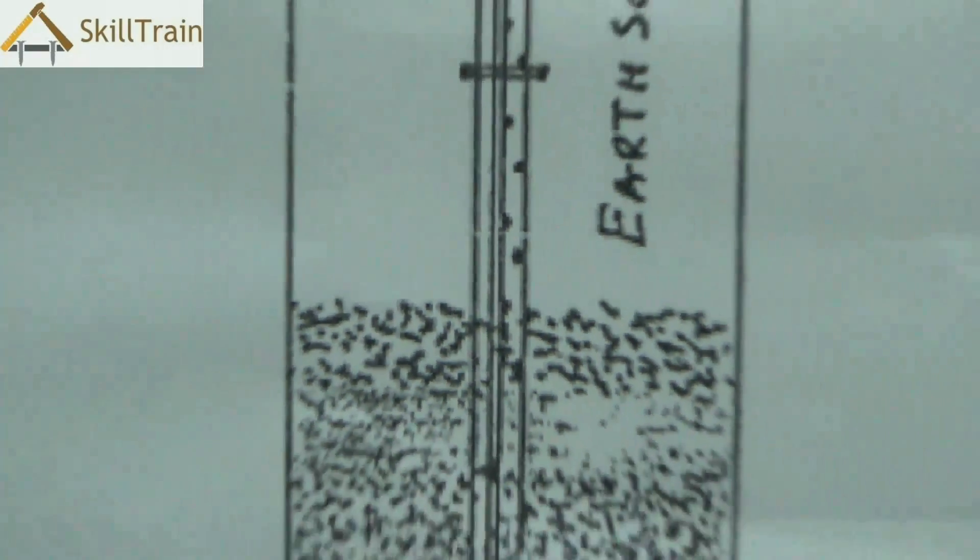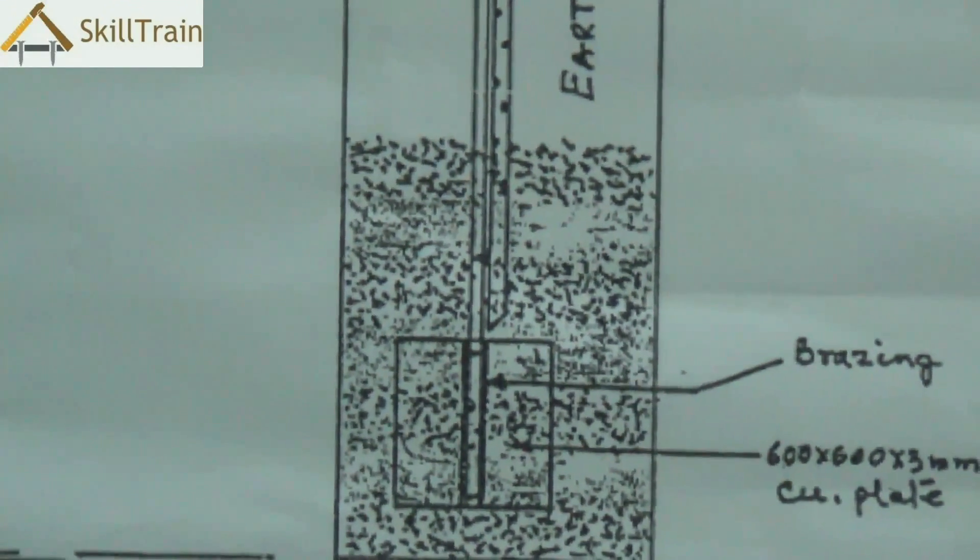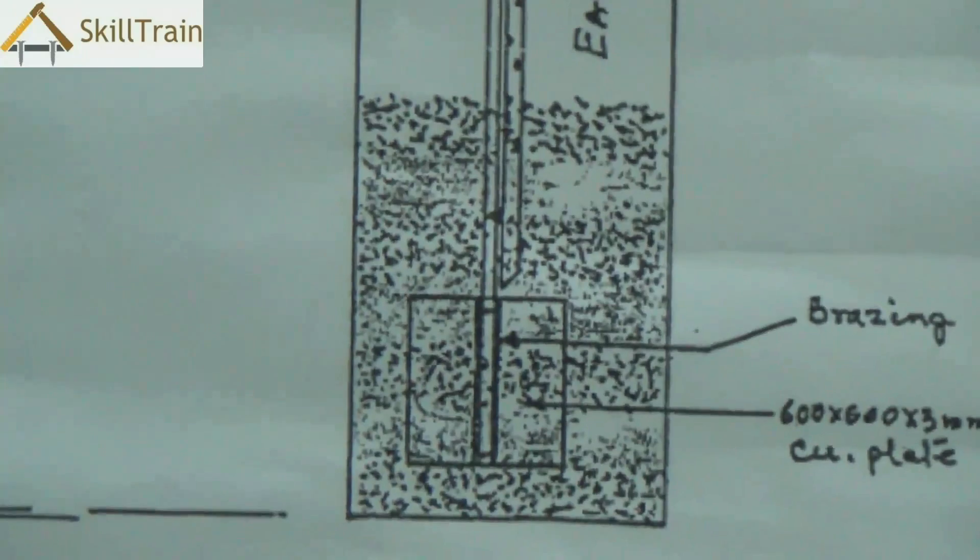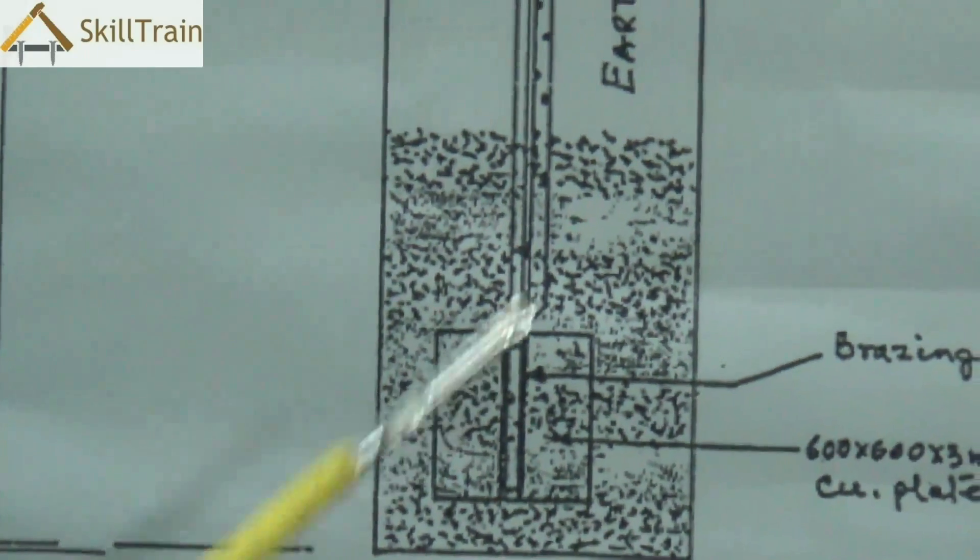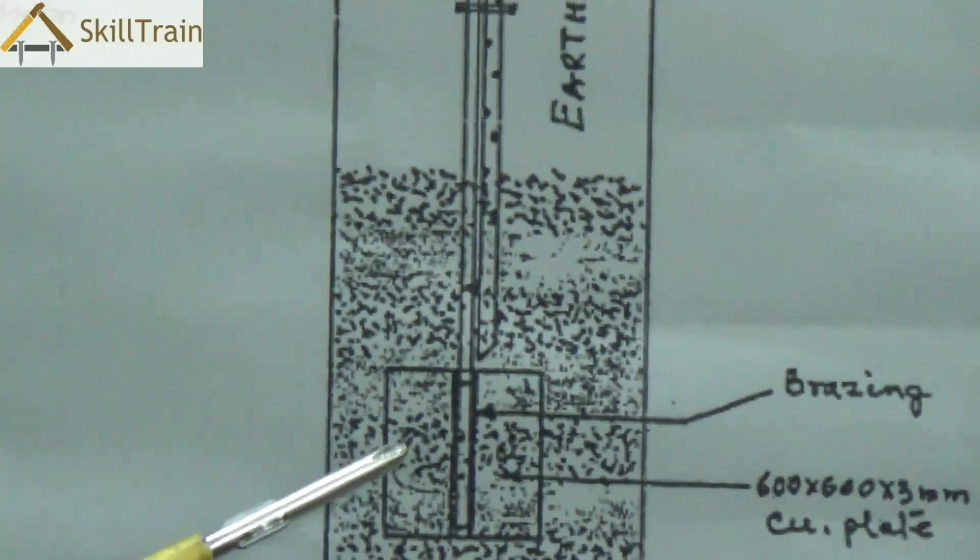Inside this we also fill it up with salt and charcoal. Charcoal essentially to maintain the humidity inside the pit and salt acts as a good ionic solution which dissipates the current that is received through the copper plate.